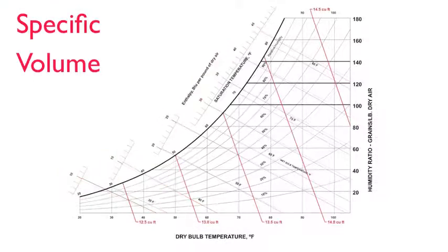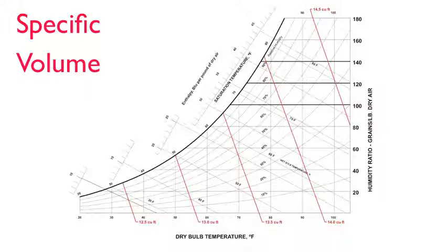Specific volume is shown by the red oblique lines equidistant from each other. This is in contrast to the wet bulb temperature lines. With wet bulb temperature, the angle is wider and the distance between the lines increases proportionately from lower left to upper right. Specific volume increases as the temperature and/or moisture increases.